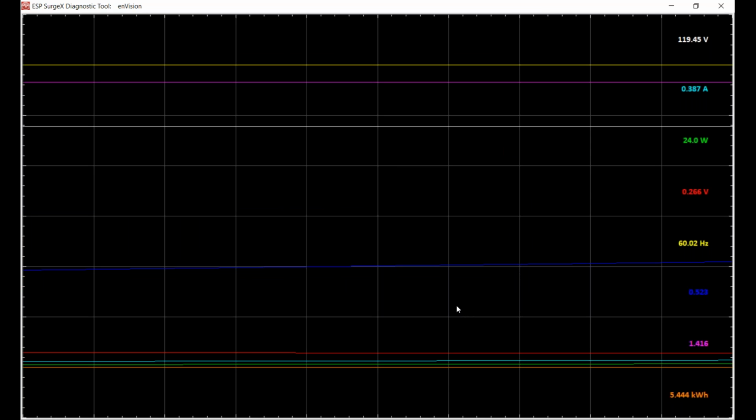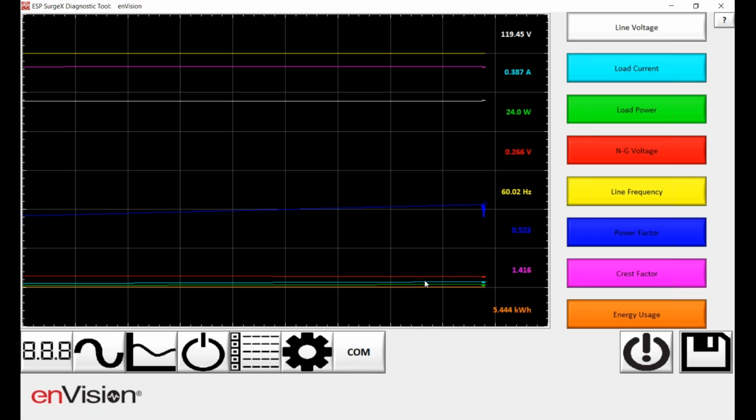It gets the measurement at that second. That's the measured value right now, and it stores that, and then it captures it again the next second and the next second. And right now, when you're running this real-time chart mode, you can see how it would trend. I always say, if you have some potentially troubled or defective equipment, go to the site, put the enVision on with your laptop running this real-time chart mode, and collect data while you're doing other things or loading the equipment or cycling it or exercising it. And then you can go back and look for trends.